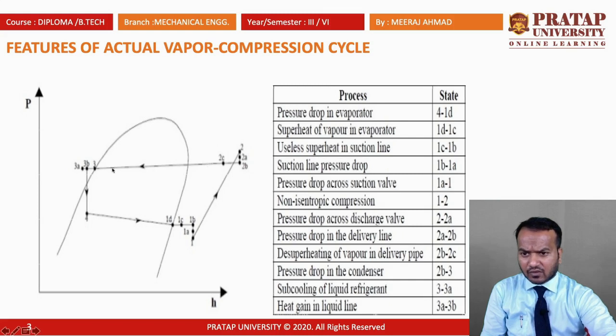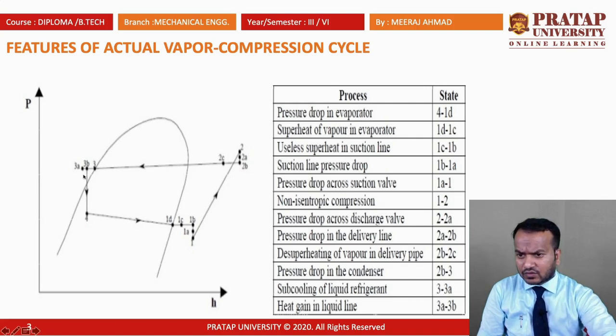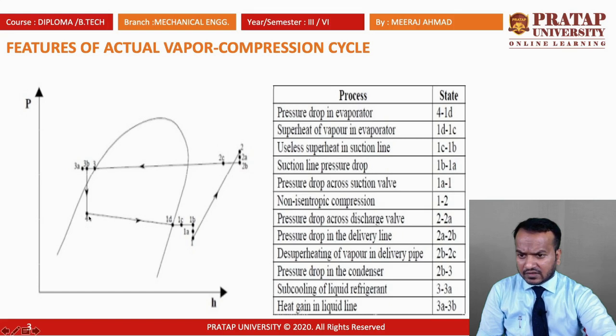From point 2c to 3 there is a constant pressure heat rejection process in the condenser, with some small pressure drop also present. Then from point 3 to 3a there is sub-cooling in the condenser. From point 3a to 3b there is further sub-cooling in the pipeline, where some heat from the surroundings enters the pipe slightly increasing the temperature. From 3b to 4 there is expansion in the expansion device.